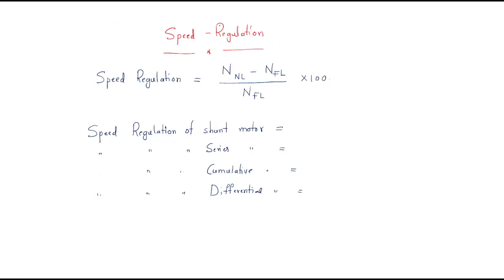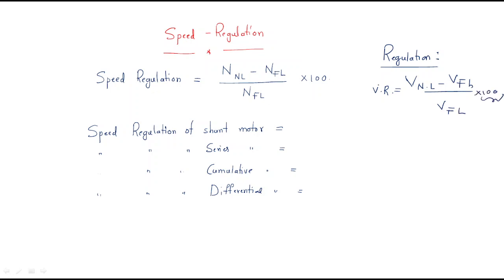The next topic is speed regulation. Just as we discussed voltage regulation for transformers — voltage regulation equals V no-load minus V full-load divided by V full-load into 100 — replacing voltage with speed gives speed regulation: speed regulation equals no-load speed minus full-load speed, divided by full-load speed, into 100. Generally, for a shunt motor, no-load speed is higher and full-load speed is lower, giving a positive speed regulation.